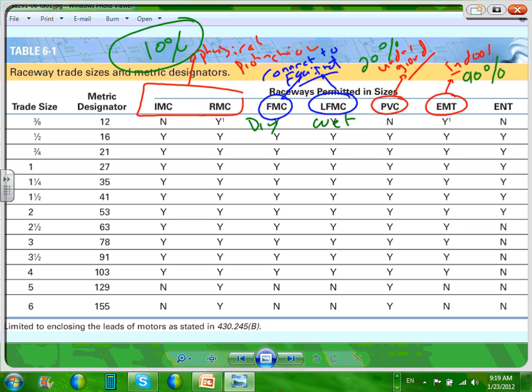Can you use that MC instead of the FMC? MC cable. Oh, yeah, thank you. MC cable. Yes, absolutely. Would I be able to use an MC cable instead of flexible metallic conduit? Yep. What's the advantage of using MC cable? You don't have to pull the conductors. What's the drawback though? Is it might not have the size, well, I guess it's more expensive, put it this way. Really the drawback, because you can have MC cables any size you can imagine, but the drawback is it's expensive.